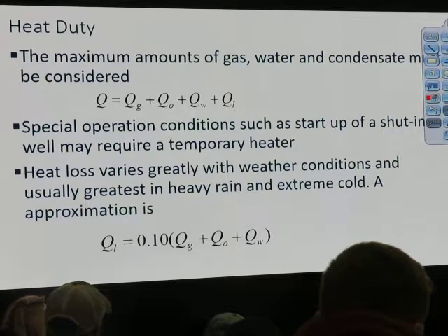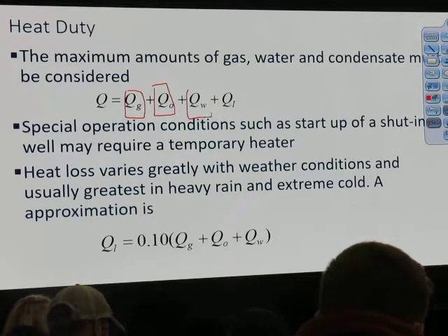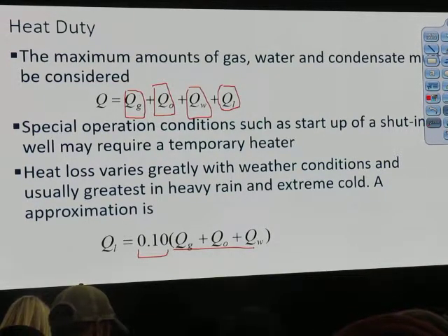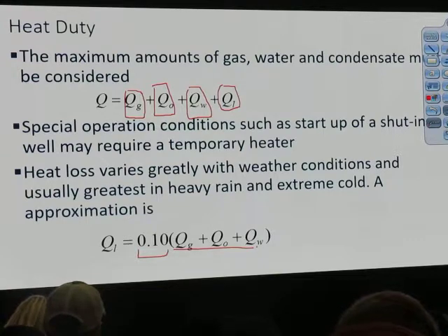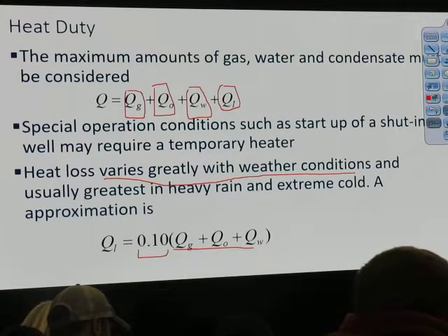Okay, heat duty. Total heat is the heat used to heat gas, the heat used to heat oil, the heat used to heat water, plus heat loss. Heat loss is estimated to be 10% of those things. But heat loss varies greatly with weather conditions. In summer, we don't have much heat loss, but in winter, we may have a lot of heat loss.